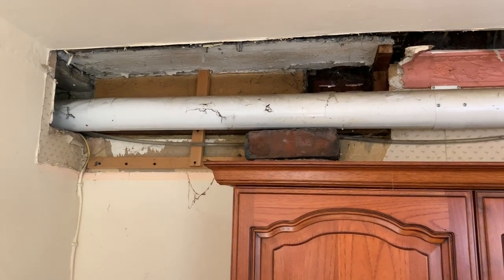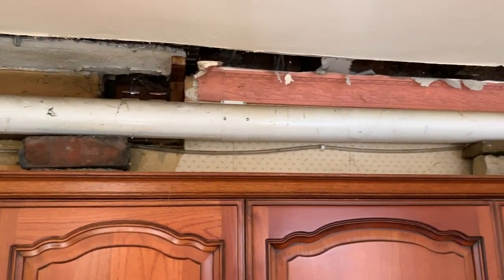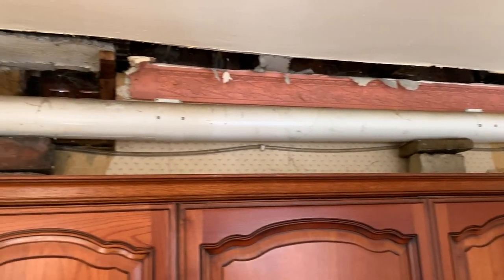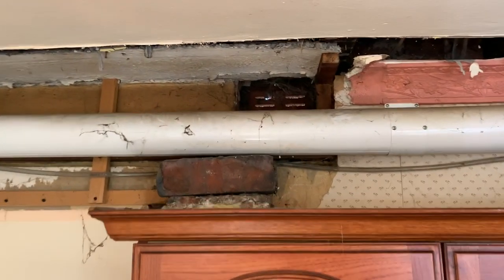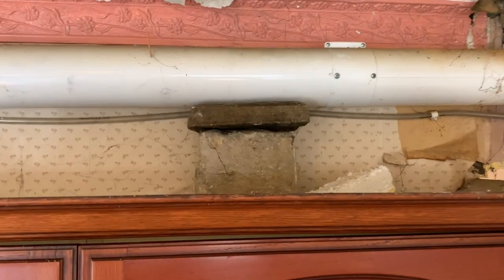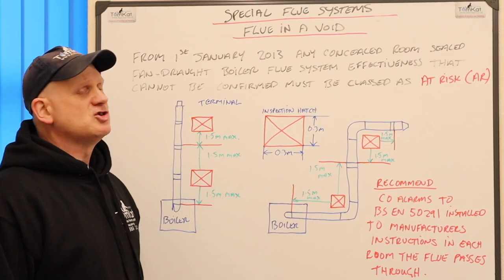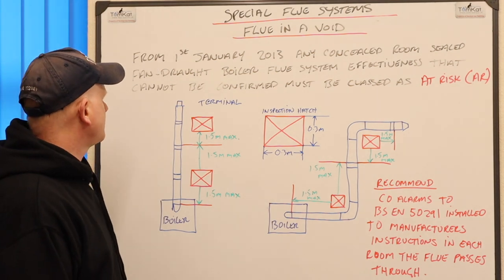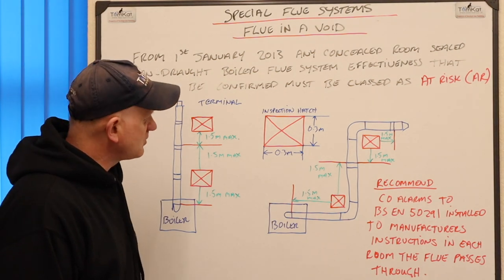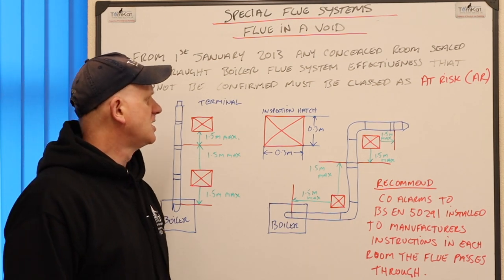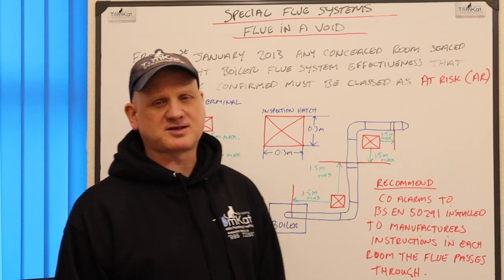This is a flue system we found when replacing a boiler — it had been boxed in, and you can see they actually used bricks instead of clips to support the flue. This is a good example of what you can find with a flue in a void. From the 1st of January 2013, any concealed room-sealed fan-draft boiler flue system where its effectiveness cannot be confirmed must be classed as at risk.